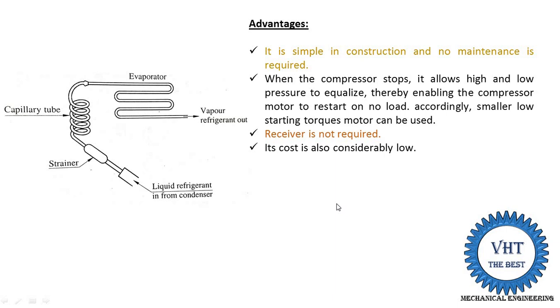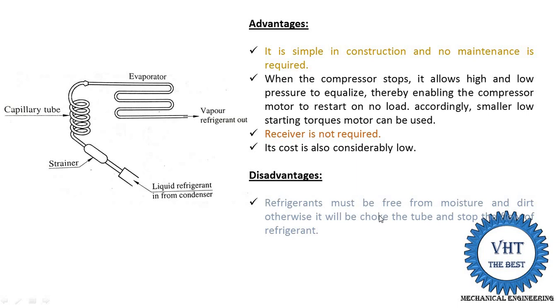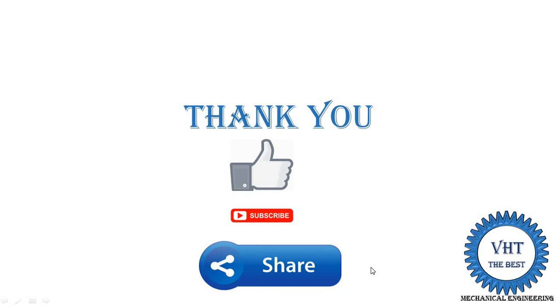The disadvantage is that the refrigerant must be free from moisture and dirt, otherwise it will choke the tube and stop the flow of refrigerant. If there is moisture inside the system, it converts into ice inside the capillary tube and chokes the system, stopping refrigerant flow. Therefore, the system must be free from moisture and dirt. Thank you for watching this video — if you learned something, please like, subscribe, and share with your friends.